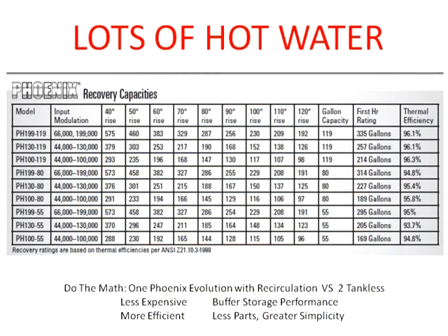Notice that there's 2-inch venting for the 130,000 BTU unit and 3-inch venting for the 199,000 BTU units. Now, this may be redundant for those who are familiar with a Phoenix, but these have very high recovery rates in terms of domestic hot water. And of course, not only that, it has the storage available. So very often, if you look at a Phoenix Evolution with a recirculation system, that can offset in a peak load condition easily 2 tankless.